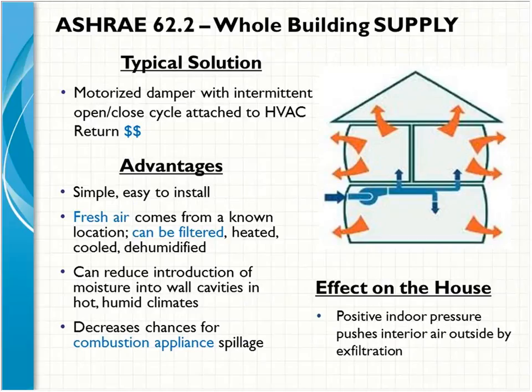All right, so let's move on to supply ventilation. Here, as I mentioned, we're relying on a duct running to a fan in the building, which is forcing air into the building and relying on the building shell to relieve that pressure. It's a little bit more expensive here because we're not just upgrading a bath fan. Now we're installing a control unit on the side of the furnace. We're installing a duct generally that runs from the exterior of the building to the cold air return. And we're operating a damper with that control as well that is normally closed until the controller says that it should open and turn the air handler on. So those are additional costs.